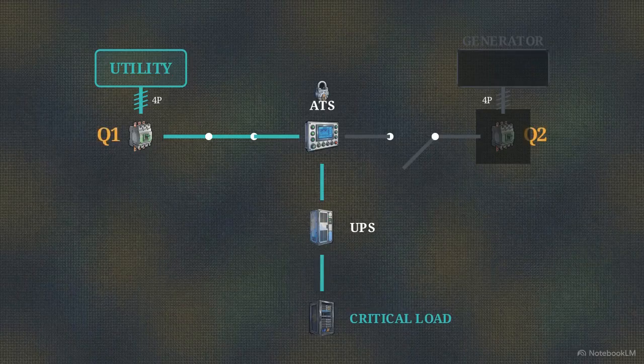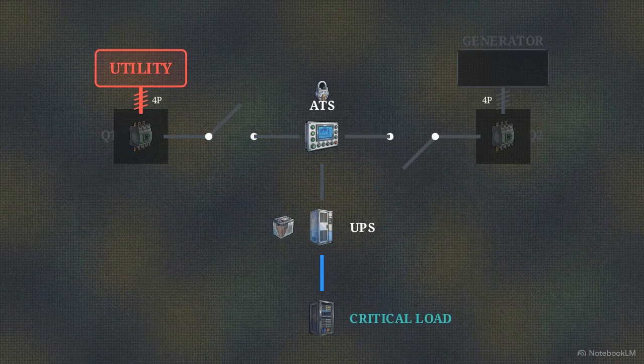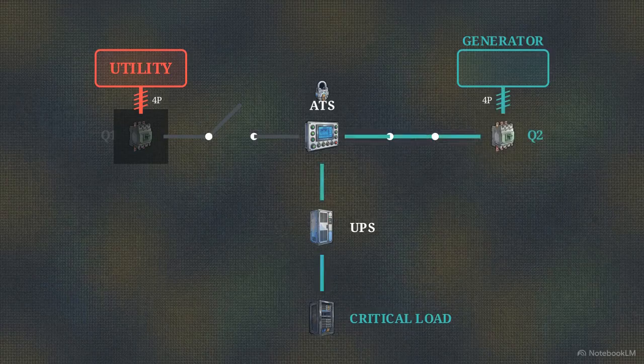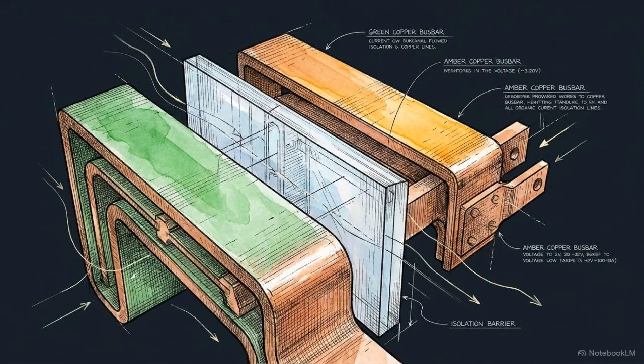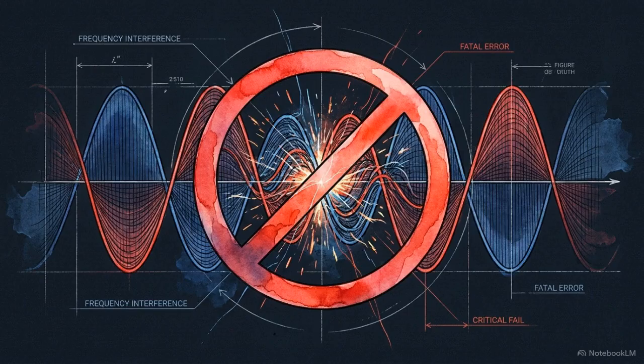To execute this safely, the system enforces a strict break-before-make sequence. The active source breaker, Q1, must open completely before the alternate breaker, Q2, is allowed to close. For a brief physical moment, neither source is connected to the bus. This physical isolation is engineered intentionally. It prevents the distinct electrical supplies from ever connecting in parallel, avoiding a catastrophic collision of out-of-phase power sources.